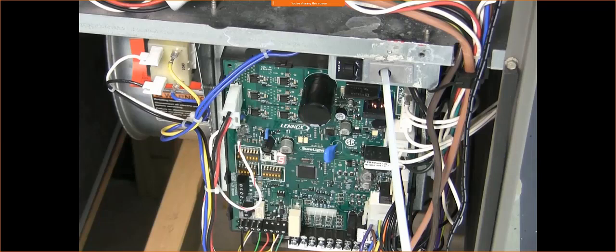So we're going to ensure that the door goes back on so the system operates properly. As technicians, we sometimes have to bypass that switch so the system runs and so we can get to and test all of our electrical components. We have our thermostat wire connections down here. We've got all these different plugs, so we need to have access to those. Using a little zip tie like this is a nice little trick to keep that safety switch in so the unit powers up.